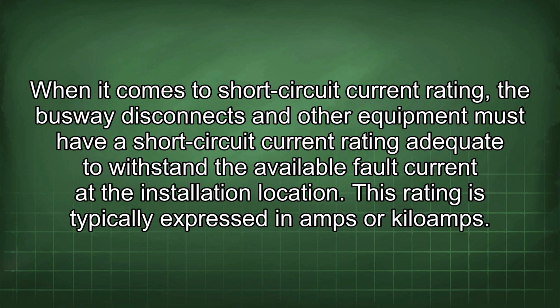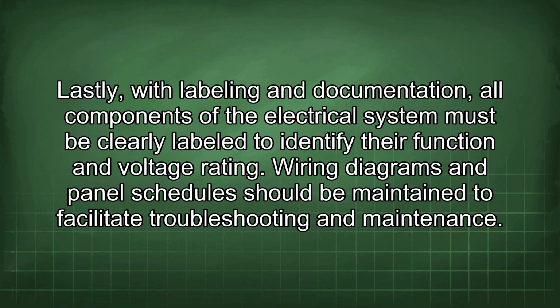When it comes to short circuit current rating, the busway disconnects and other equipment must have a short circuit current rating adequate to withstand the available fault current at the installation location. This rating is typically expressed in amps or kiloamps. Lastly, with labeling and documentation, all components of the electrical system must be clearly labeled to identify their function and voltage rating. Wiring diagrams and panel schedules should be maintained to facilitate troubleshooting and maintenance.